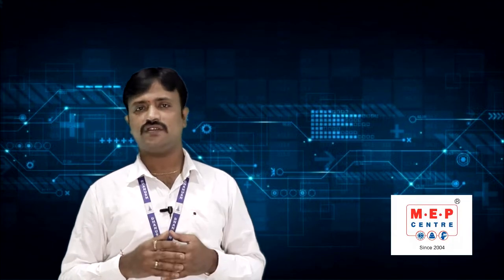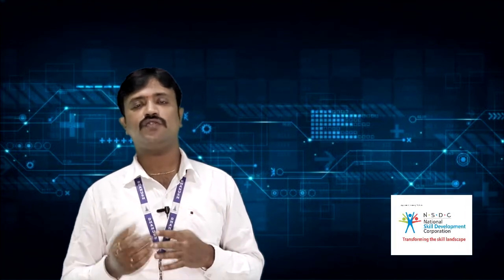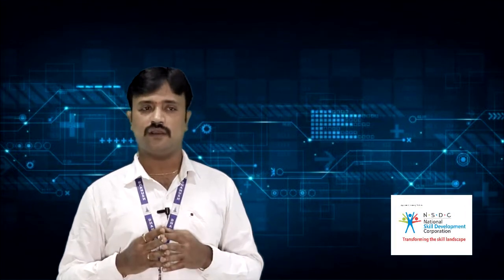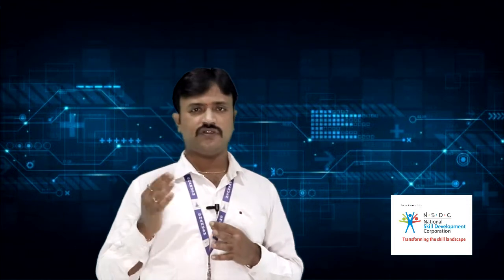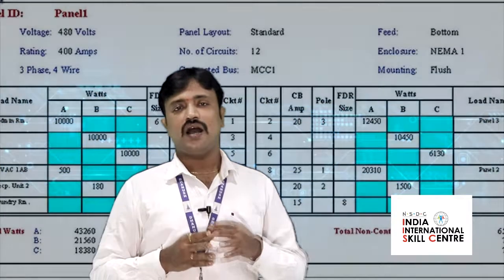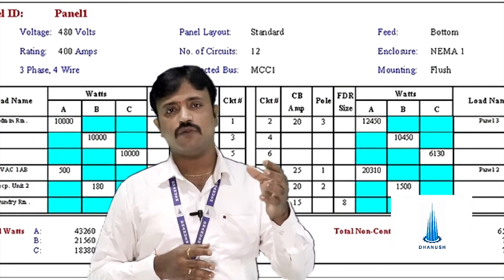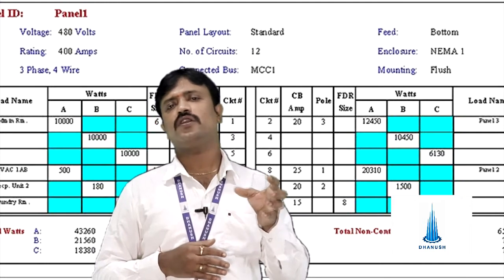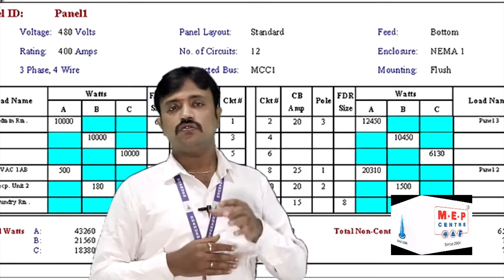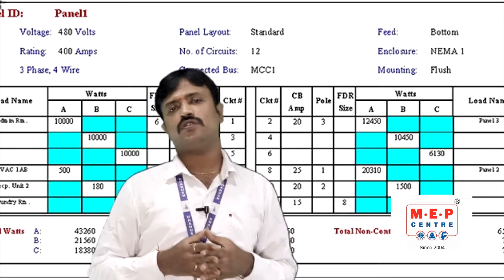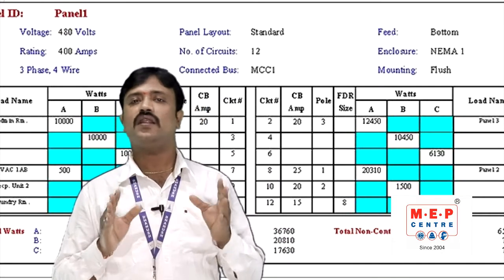If your flat load is up to 8 kilowatt, you can take it from single phase. If your flat load is above 8 kilowatt, or if the submersible pump which you are placing in your home is above 3 HP, then we need to bring 3 phase supply for the building. Okay, now the question is, I have brought 3 phase supply for a building. Now the most important thing we need to do is the load balancing sheet, because I got a total load, for example 12 kilowatt. I need to balance this 12 kilowatt equally across three different phases. So to do this, the most important model we are going to learn is the load balancing sheet.